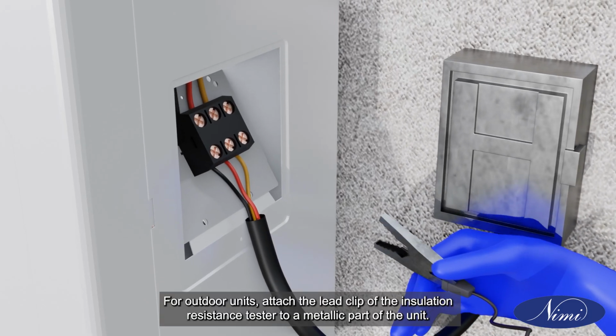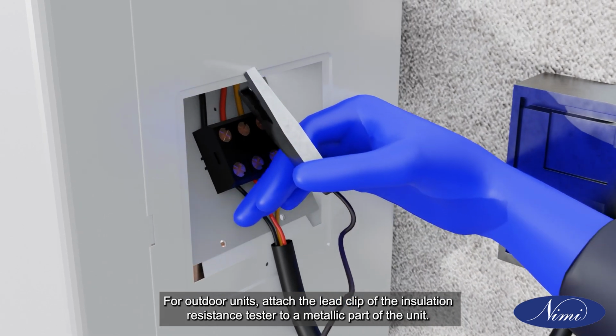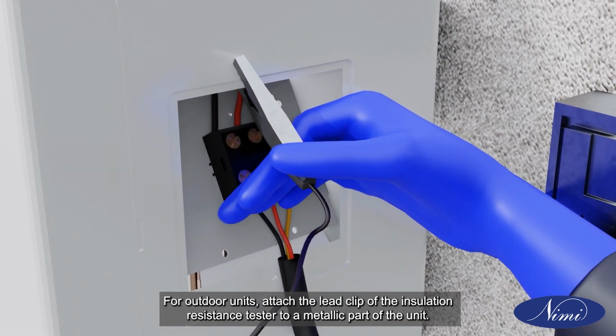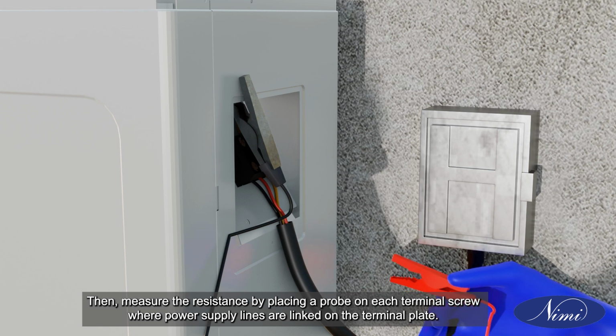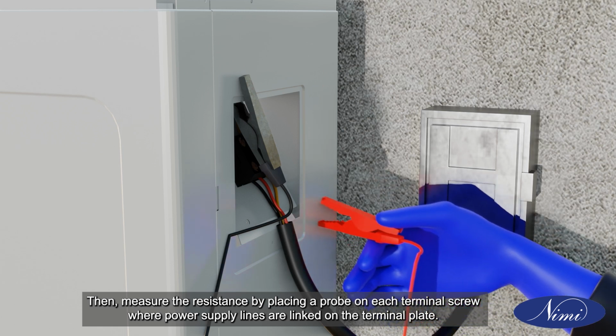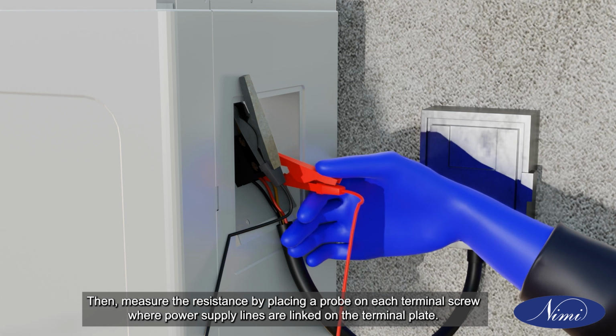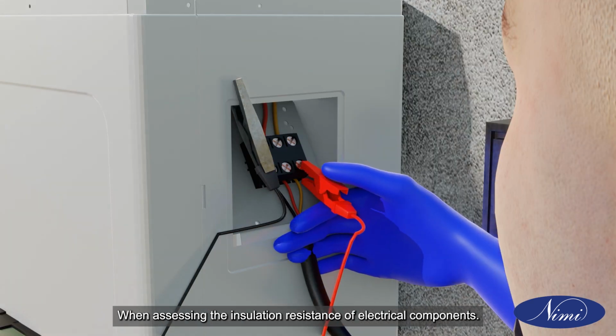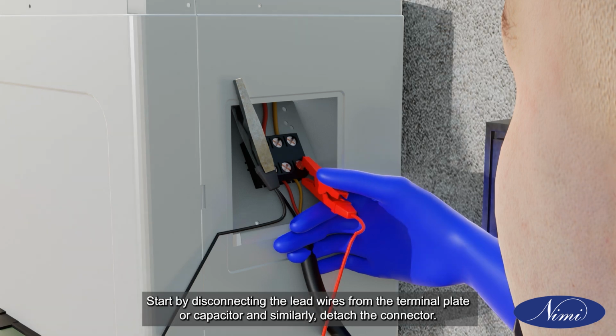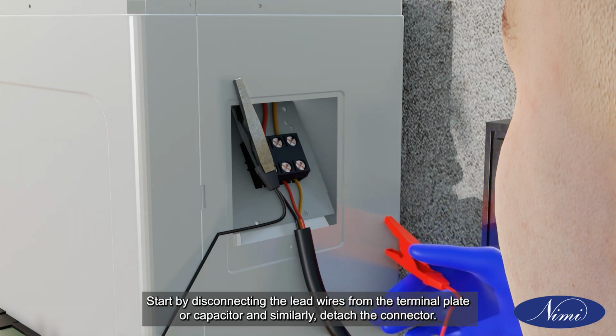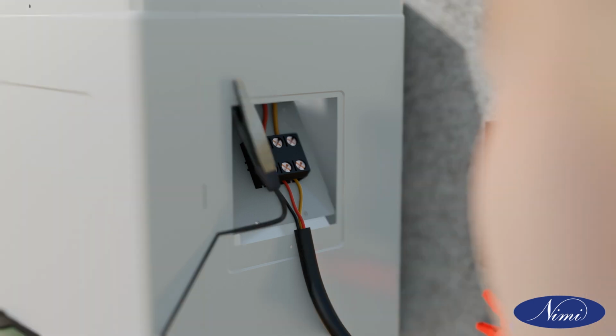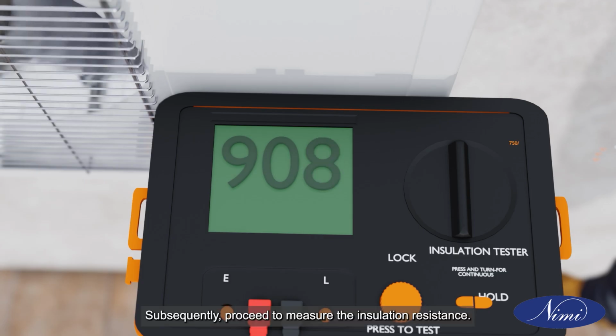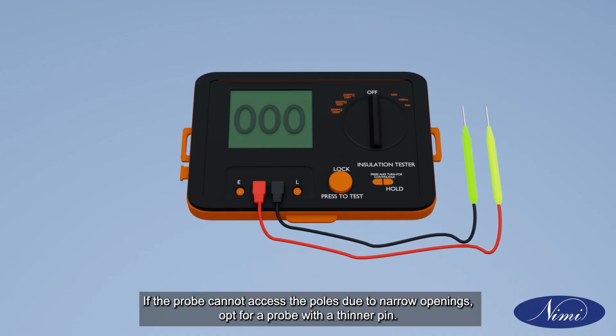For outdoor units, attach the lead clip of the insulation resistance tester to a metallic part of the unit. Then, measure the resistance by placing a probe on each terminal screw where power supply lines are linked on the terminal plate. When assessing the insulation resistance of electrical components, start by disconnecting the lead wires from the terminal plate or capacitor and similarly detach the connector. Subsequently, proceed to measure the insulation resistance. If the probe cannot access the poles due to narrow openings, opt for a probe with a thinner pin.